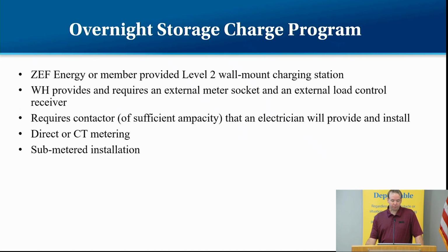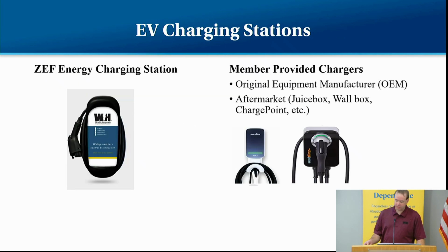The overnight storage program is quite similar. You can use either a ZEF Energy or a member-provided level 2 wall-mounted station. We will again provide the external meter socket and the load control device. However, it will require a contactor of sufficient ampacity that the electrician would install. We do not provide the contactor, so that would be the electrician or the member providing that. It could be direct or CT metered, and it would be a sub-metered installation. For the EV charge stations, we have the ZEF Energy charging station, or the member provided, whether it's Ford, Tesla, aftermarket, JuiceBox, Wall Box, ChargePoint, any of those.